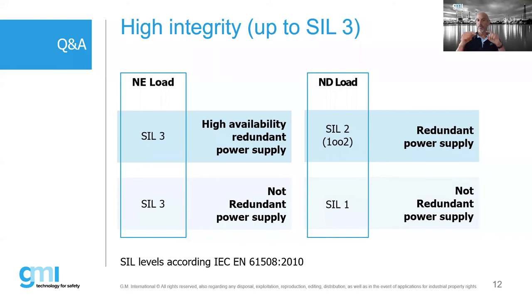Maybe we had some problem with the previous slide. That is also important. If you look at these pictures, looking at a normally energized load, if I have a SIL3 power supply, not redundant, just one power supply, I can achieve the SIL3 level. If I use a redundant system, two power supplies powering the same plant, I have the same safety, SIL3, but I also have high availability, because one power supply can fail and the other will continue working. So it means I have high safety and also high availability.